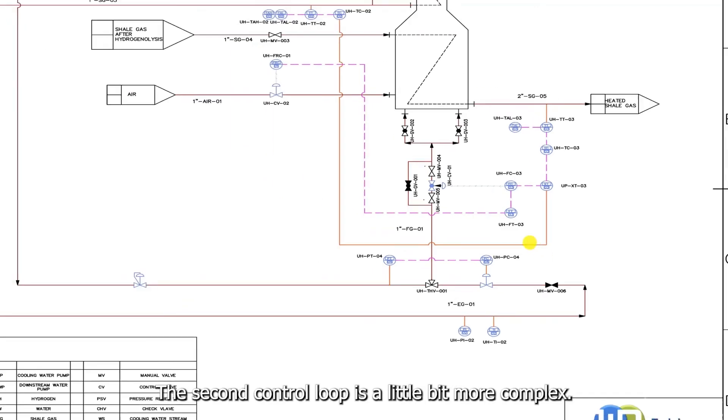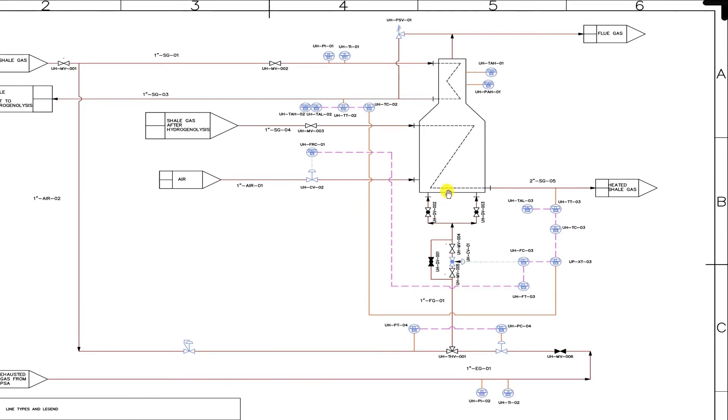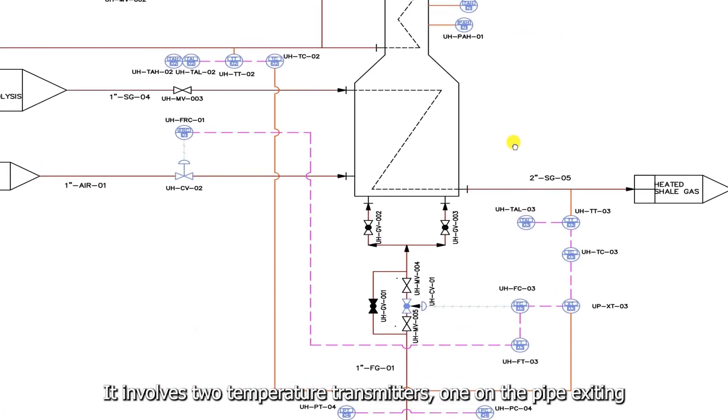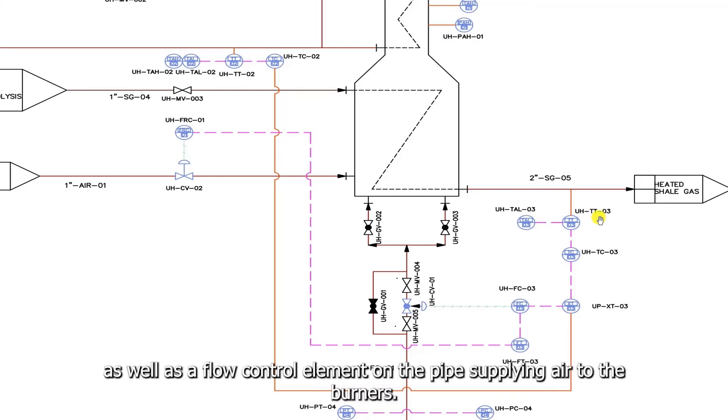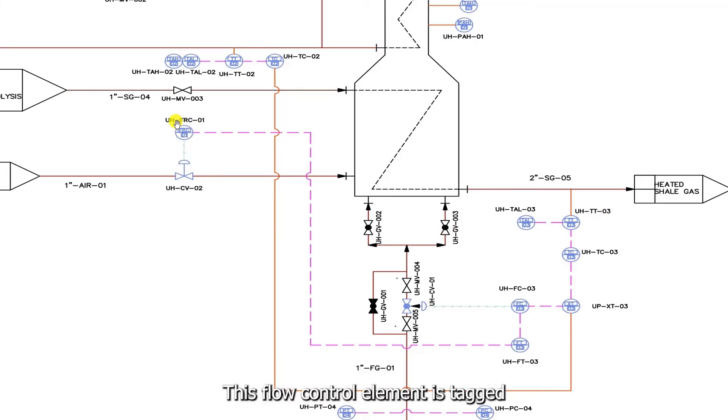The second control loop is a little bit more complex. It involves two temperature transmitters, one on the pipe exiting the convection zone, tag TT-02, and another on the pipe exiting the radiation zone, tag TT-03. As well as a flow control element on the pipes supplying air to the burners. This flow control element is tagged FRC-01. Recall, FRC stands for Flow Recording Controller.